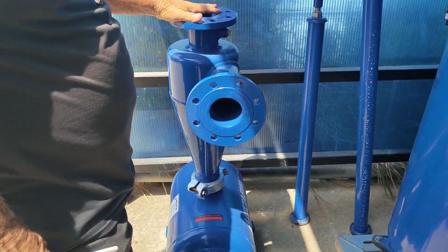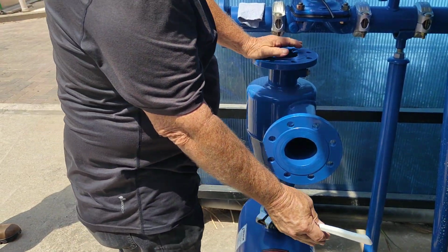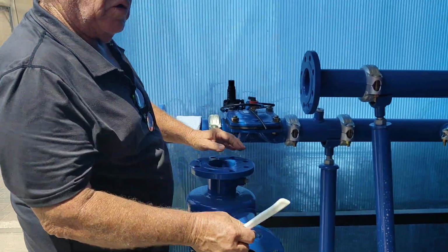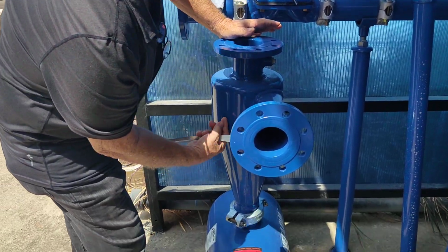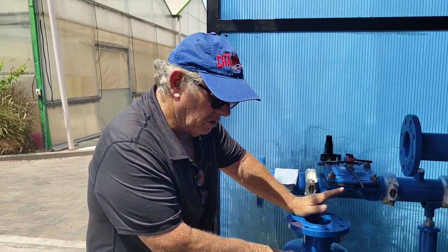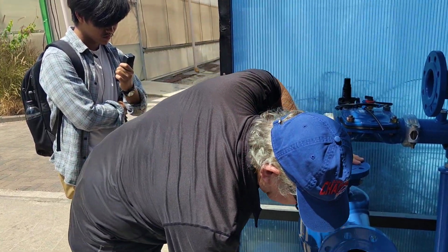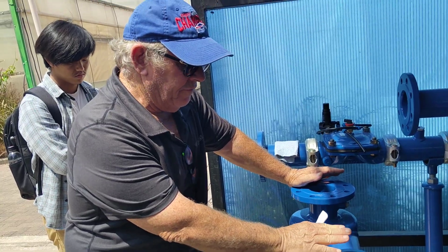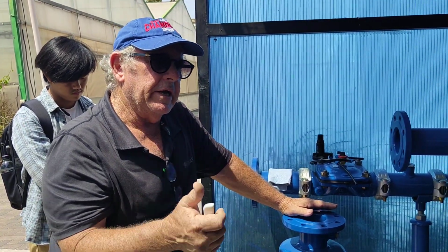Another thing is the hydrocyclone, as you can see here. Unfortunately it's not open, but anyway, I can control the pressure. This is the inlet, the pressure which comes from here, and the outlet, and I can control it by valve to make a delta P of 5 meters, which is 0.5 bar. I will create circulation here. This circulation permits the sand to separate. This is a sand separator. There is no element inside. The circulation will create some pool of sand which will go to the tank, and from time to time we open it and clean it. This is the functionality of the hydrocyclone or sand separation, to remove iron and sand.